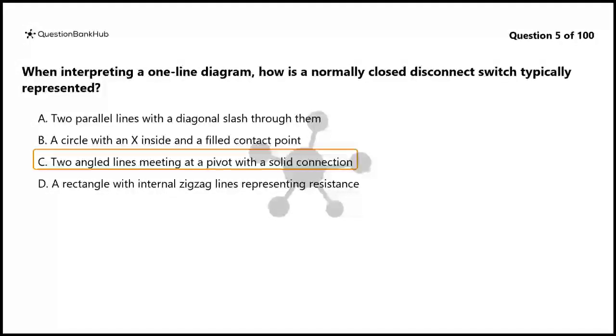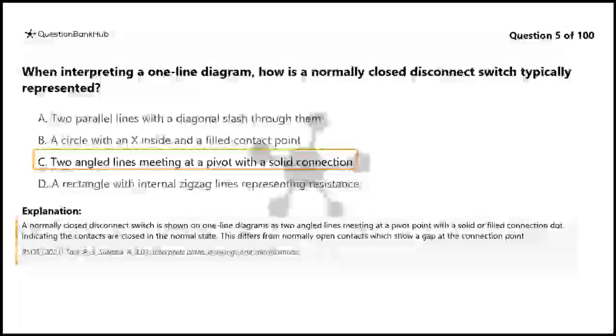The correct answer is C. Two angled lines meeting at a pivot with a solid connection. A normally closed disconnect switch is shown on one-line diagrams as two angled lines meeting at a pivot point with a solid or filled connection dot, indicating the contacts are closed in the normal state. This differs from normally open contacts which show a gap at the connection point.